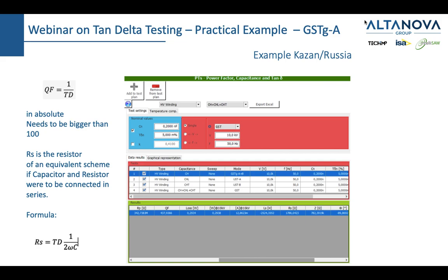But also, let me tell you that this test set can also be used to measure tan delta on cables. The cables have this, let's say, issue in which the capacitance is much, much bigger. If you were to have a medium voltage cable up to 20 kilovolts and with a standard of 0.36 microfarads per kilometer, you would be able to measure maybe even up to 3.6 kilometers. This is a quick calculation, but for sure, how big a cable you can test depends on the voltage level of the cable and the capacitance per kilometer. In some cases, if you purchase a reactor, which is just an additional inductor, you would be able to extend that.